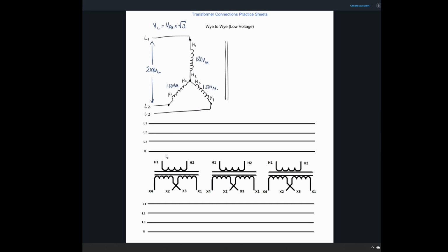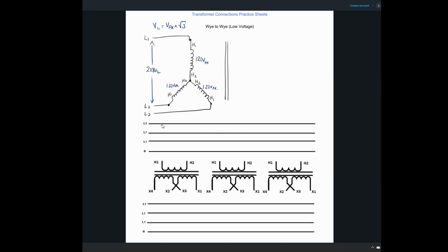Let's use that in order to wire the primary here first. We've got line 1 going to H1. Okay, and all of our 2's are going to be joined together. So this guy is going to go to this center point right here, but it's not actually connecting outside of the circuit, right? I didn't bring 4 wires in. I only brought 3 wires in to that circuit. So I'm not going to bring that to the neutral because I didn't provide a neutral there, but I am going to tie all of those guys together.